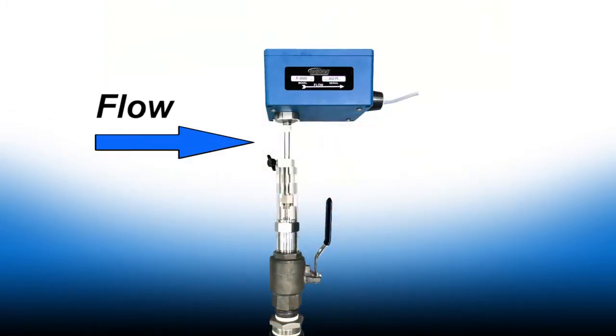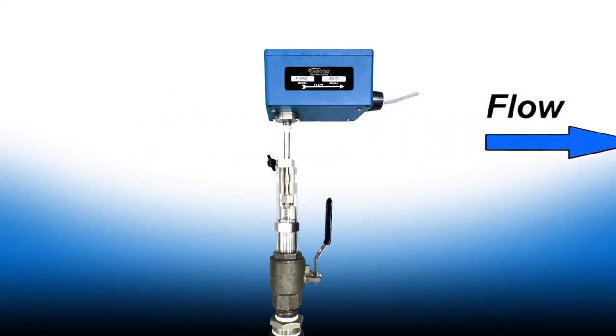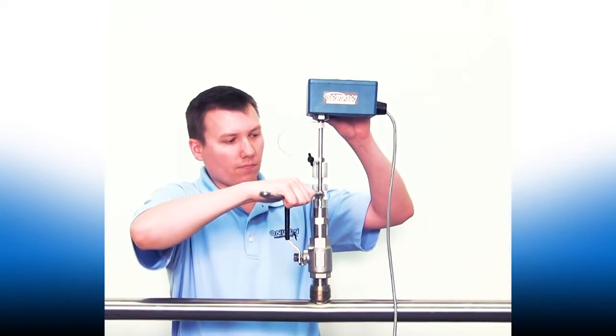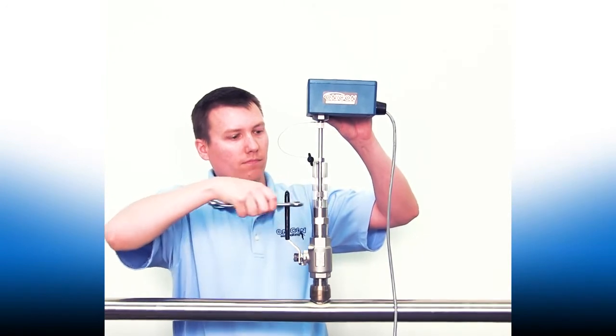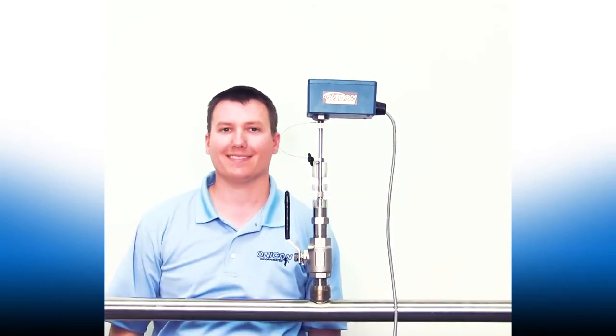Make sure the flow direction on the meter is pointed in the direction of flow in the pipe. Tighten the clamping nut with an adjustable or a five-eighths inch wrench to set the depth and orientation.